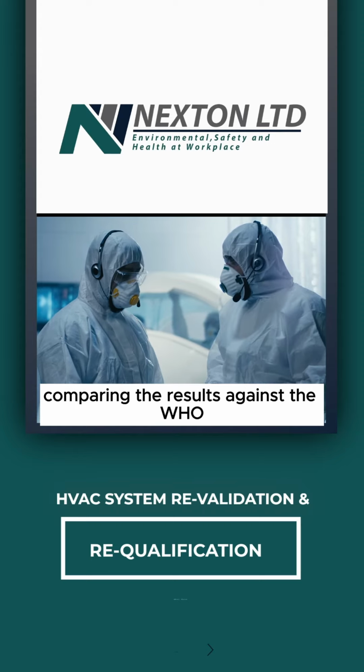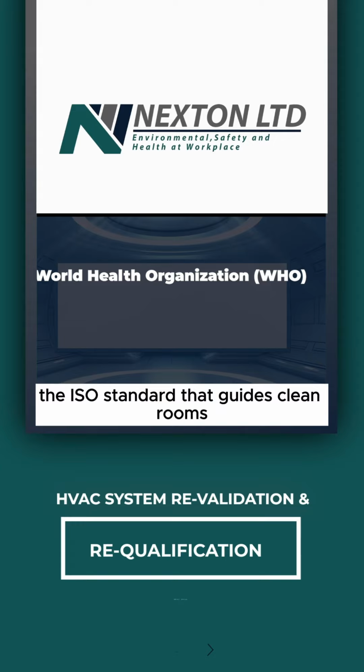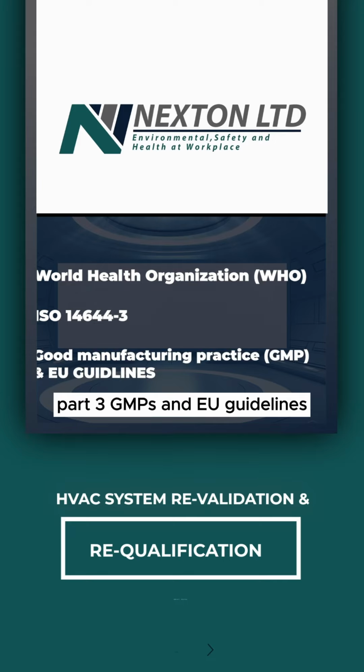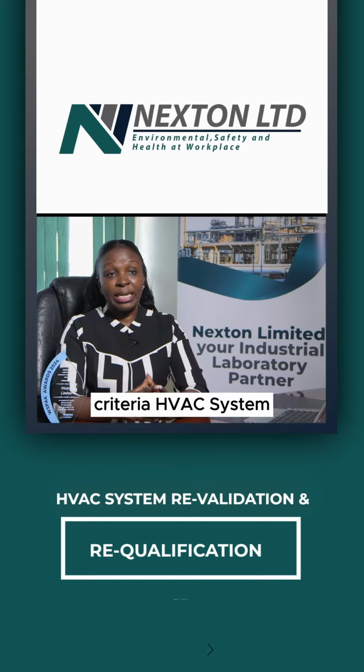requirements, comparing the results against the WHO, the ISO standard that guides clean rooms, which is ISO 14644 Part 3, GMPs and EU guidelines. And these results again are compared in order to see if they meet the original design criteria.